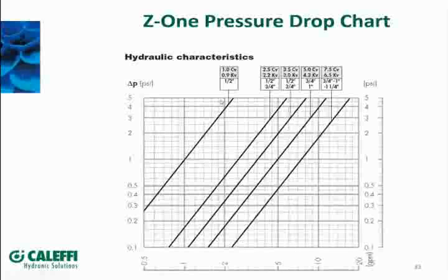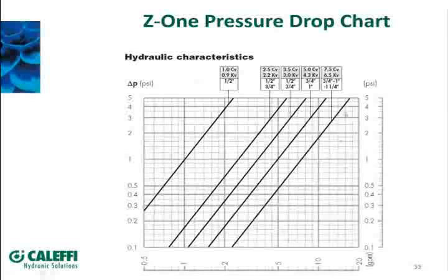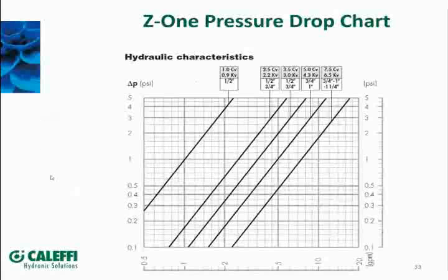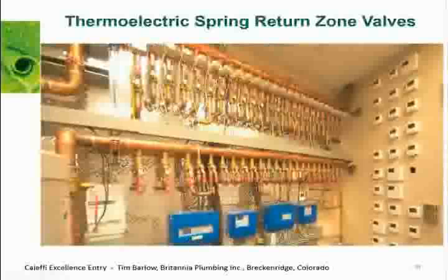This graph shows our Z1 valve at different CV ratings and the characteristics of each. Let's say we're going to flow two gallons per minute through a valve. Come to two GPM on the bottom and run up the line — you can see that with a smaller CV of one, the pressure drop at two-gallon flow is up around four PSI. Whereas with the five CV valve, come down at two GPM and you can see how low the pressure drop is. That chart helps you decide what the application is and which valve is best for the job.